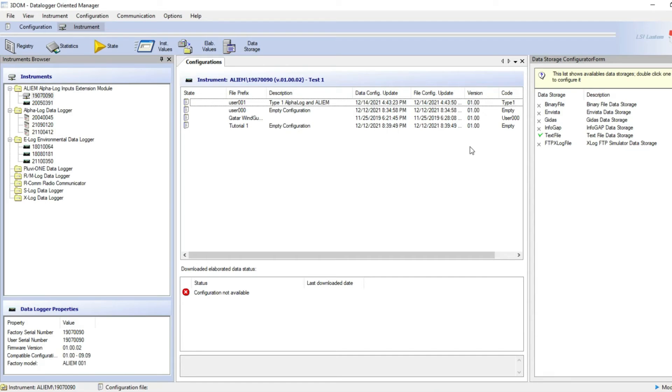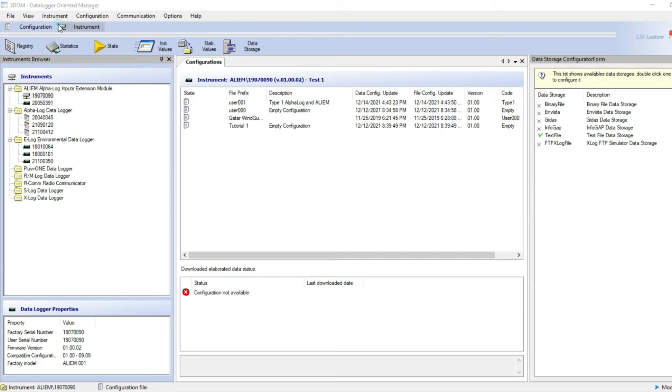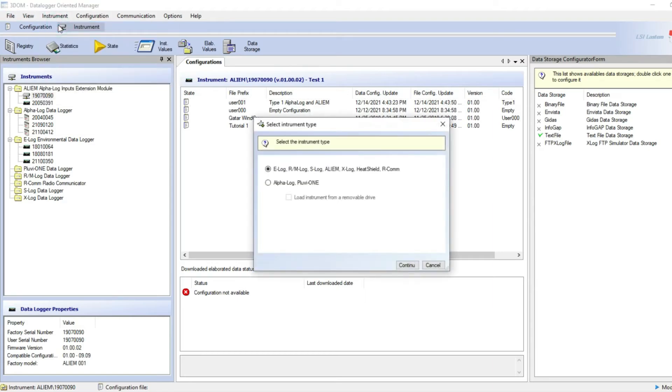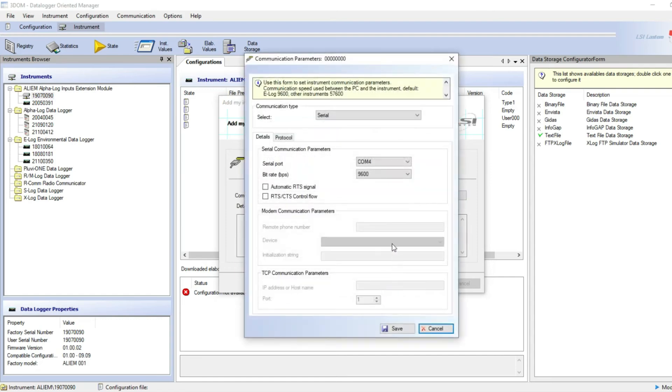Open 3DOM, go to instrument and click on new. Select E-Log as instrument type and click on continue and next. Choose the serial port you found on the control panel as described before and select 9600 as bit rate.